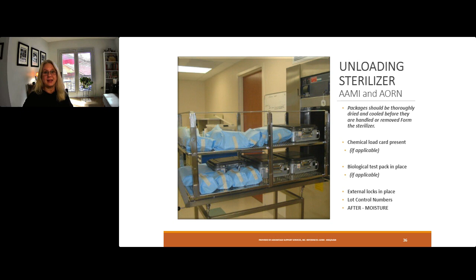Sterilization records, I'm going to say, need to be inspected on every shift. And I know a lot of people do them maybe at midnight, weekly audits, but I want to suggest that because this is a legal document, we're held accountable to it. It really assures the level of sterility, especially for auditors that come in and inspect your processes, to inspect those records on every shift. At the end of the shift, you can appoint a certain important person, lead tech, supervisor, to audit those records. A lot of times they're on paper and held within an envelope, or they're electronic, and both need to be inspected to make sure that we have initialed and documented everything. It is a legal document.